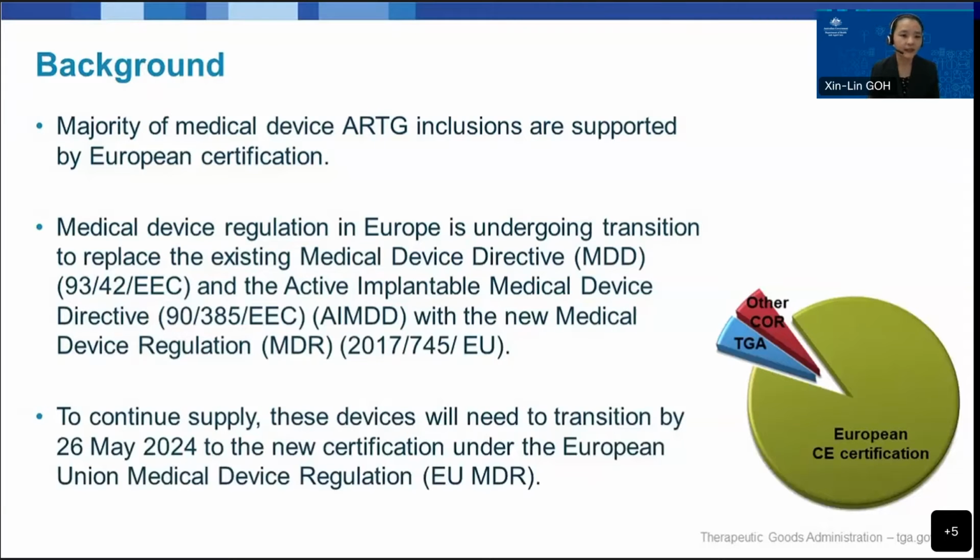So in Australia, most medical devices in the ARTG are supported by European certification. And in 2017, a major update to medical device regulations in Europe was introduced. The new European medical devices regulations replace the medical device directives and the active implantable medical device directives. This transition ends on the 26th of May 2024, where devices supported by EU MDD certification will need to transition to the new EU MDR certification in order to continue supply.